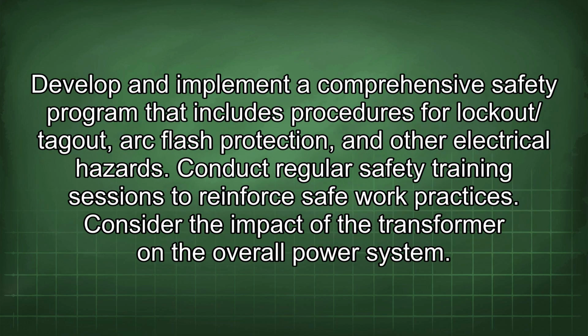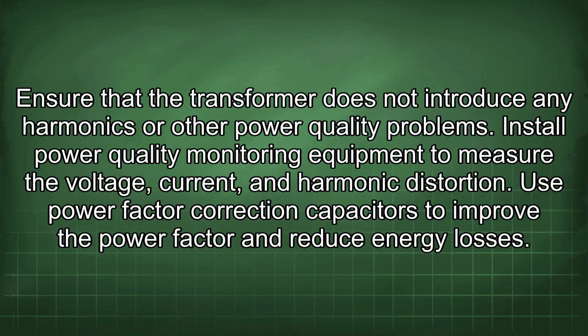Develop and implement a comprehensive safety program that includes procedures for lockout/tagout, arc flash protection, and other electrical hazards. Conduct regular safety training sessions to reinforce safe work practices. Consider the impact of the transformer on the overall power system. Ensure that the transformer does not introduce any harmonics or other power quality problems. Install power quality monitoring equipment to measure the voltage, current, and harmonic distortion. Use power factor correction capacitors to improve the power factor and reduce energy losses.